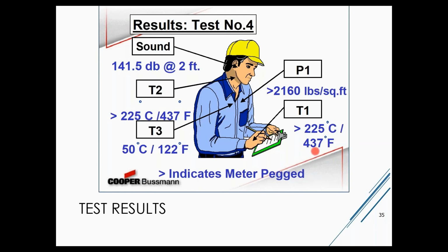If you look at this, we know that the heat was at least 437 degrees and certainly higher than that on the outside. But you look at the 122 degrees Fahrenheit on the inside of the shirt under the garment, which was below that second degree burn threshold. So the garment did its job. And to me, that's one of the most important points, or one of the real highlights of basic 70E, is to realize that the garment will protect you from that thermal value. The tough part is dealing with the pressure waves. It's very difficult, if not impossible, for a cloth garment to provide any real degree of arc blast protection. But again, that's a discussion for a longer day.